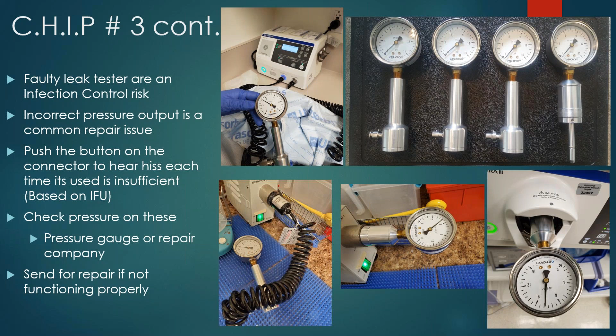Now, right now we're in the early preliminary studies, and traveling across the country there's a few of us doing this study. Already, we're finding that out of 13 pieces of equipment, which includes the unit and accessories, 11 of them are failing. So much so that a couple weeks ago, when I tested at one facility, the lever, the little gauge, didn't even move at all. And that was something they were using every day, every time. So they pulled out their backup, and the backup failed. So again, this is something we're finding consistently, and this will probably be the first time you're hearing about this. But again, making sure that your units are properly functioning is a big issue.